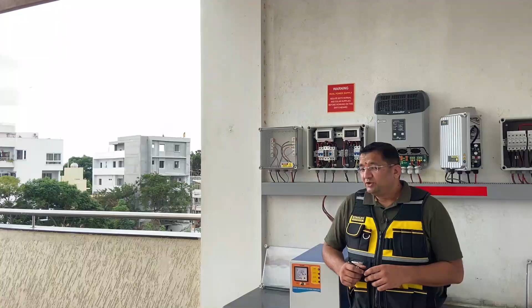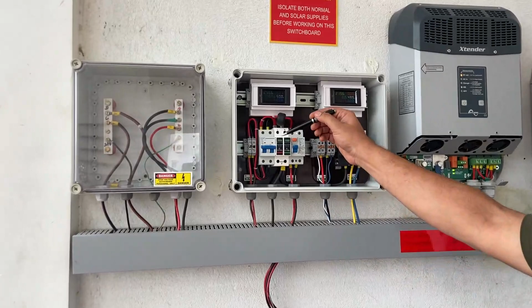From there, one line is tapped, it goes into the relay and another SPD there, and it comes to the distribution box. Even before it gets into the distribution box, the power gets into this servo stabilizer. The stabilized output from this stabilizer gets into the input side of the inverter. See, before the power gets into the inverter, this is the input panel. In the input panel, we have got a MCB, we have got a 275 volts SPD, we also have a ELCB. This is the meter which measures the various parameters of the input power.